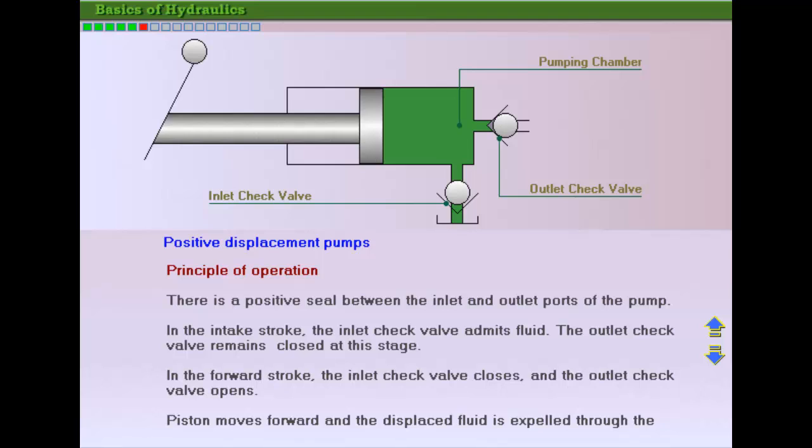On the forward stroke, the inlet check valve is forced closed, sealing off the inlet from leakage back to the reservoir. The piston moves forward and pressure is created by resistance to flow as the outlet check valve opens and the pump's displacement of fluid is pushed out to the system.